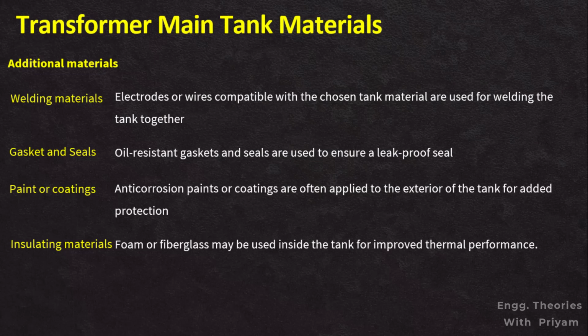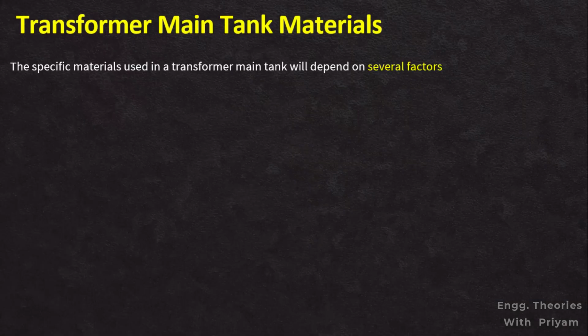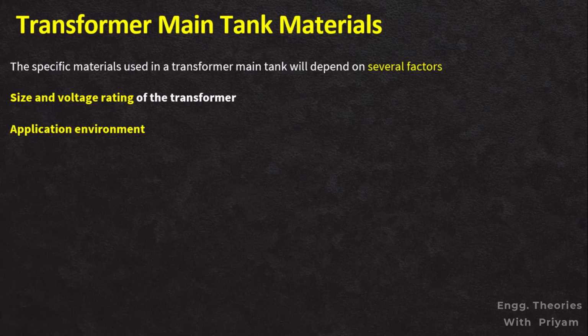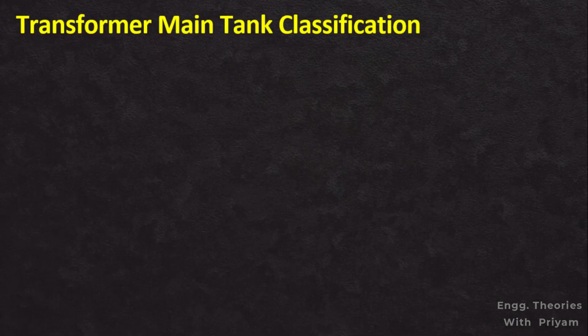The specific materials used in the transformer main tank will depend on several factors, including size and the voltage of the transformer. Larger and higher voltage transformers typically require thicker and stronger tank materials. Application environment. For outdoor applications, corrosion resistant materials like aluminum or stainless steel might be preferred. Cost consideration. Steel is generally the most cost effective option, while aluminum and stainless steel offer additional benefits at a higher cost. Let's explore the classification of the transformer main tanks.